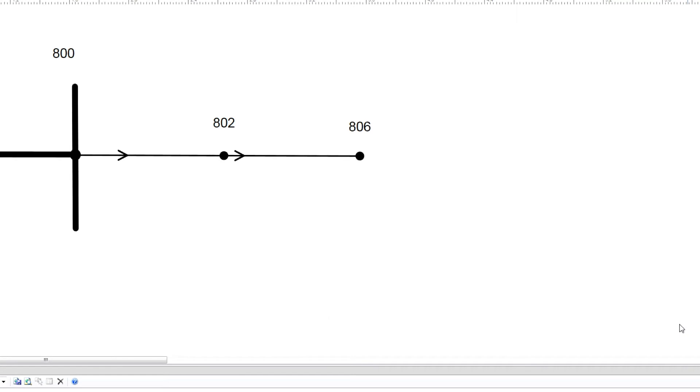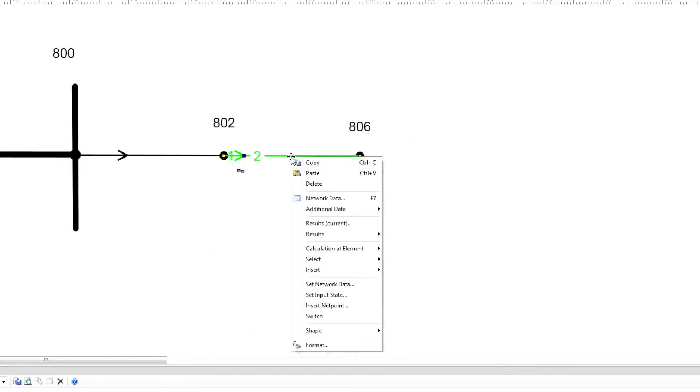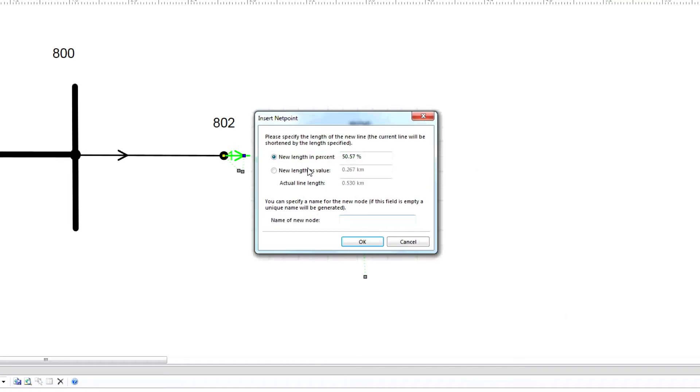Next, we must create a load model. In this example, we will model a distributed load at the middle of two nodes which is half the length of the line. Start by splitting the line in half. Click on the line and check the present length. Now right-click, choose insert net point, select new length in percent, 50%, and then provide the new node name. We'll use distributed load 802 to 806. Click OK and double check your changes.